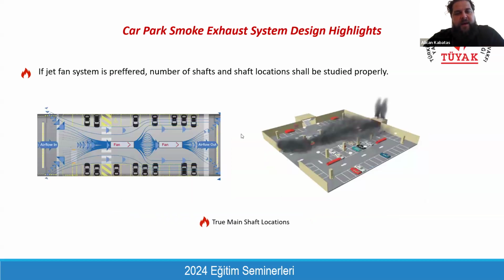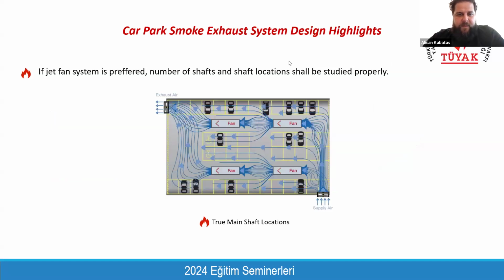As you can see, this is the proper shaft location. The fresh air comes from this side, and jet fans take the smoke and put it on the other side, and by this extraction shaft, it is exhausted.